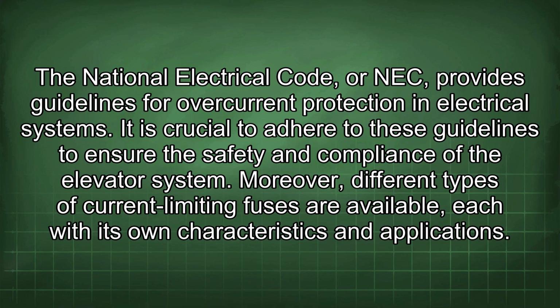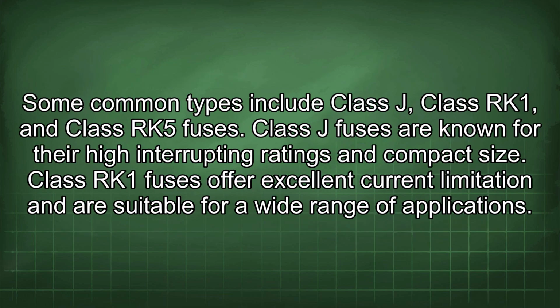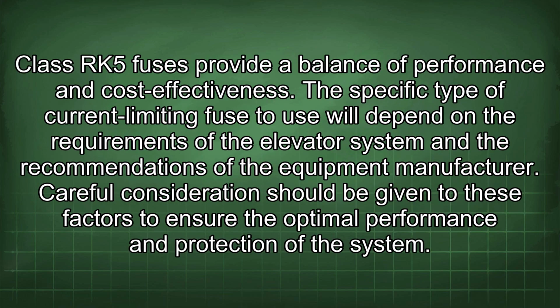Moreover, different types of current-limiting fuses are available, each with its own characteristics and applications. Some common types include Class J, Class RK1, and Class RK5 fuses. Class J fuses are known for their high interrupting ratings and compact size. Class RK1 fuses offer excellent current limitation and are suitable for a wide range of applications. Class RK5 fuses provide a balance of performance and cost effectiveness.